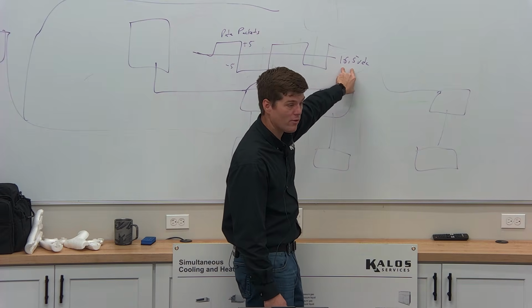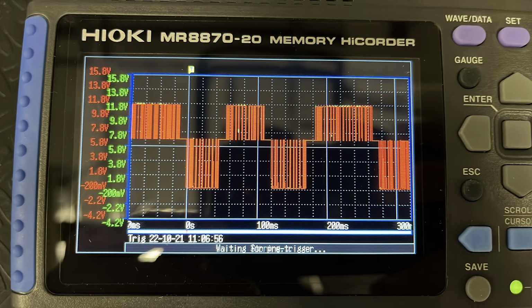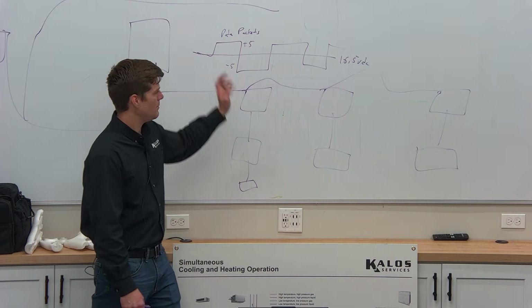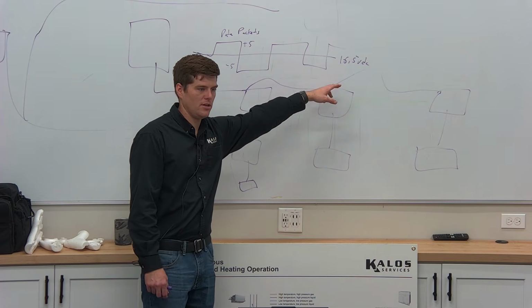That 15.5 volt carrier wave is going to then do these plus and minus 5 volt packets in milliseconds that you'll never see to talk to each other. So you're really only concerned about, okay, I can't see that fan coil. It's not working. It's got an error code, U4, which is communication error. Let me check. Okay, 15.5 volts DC. No, I don't have it.